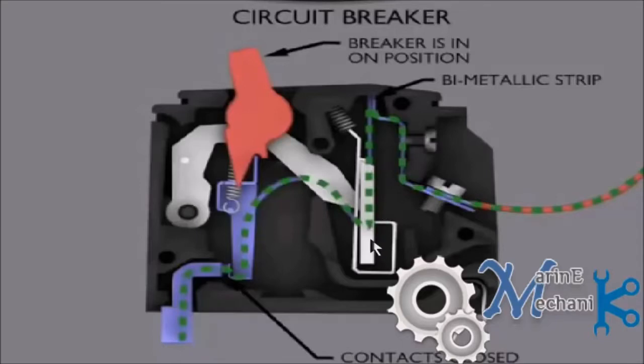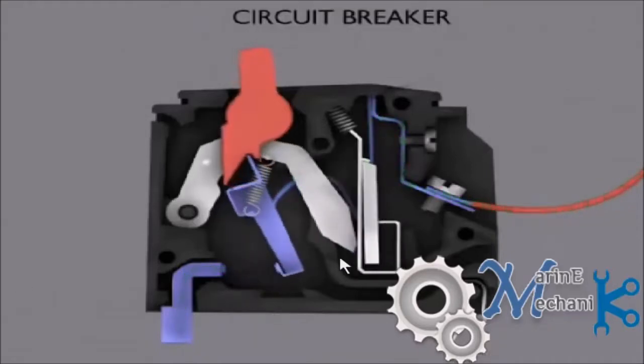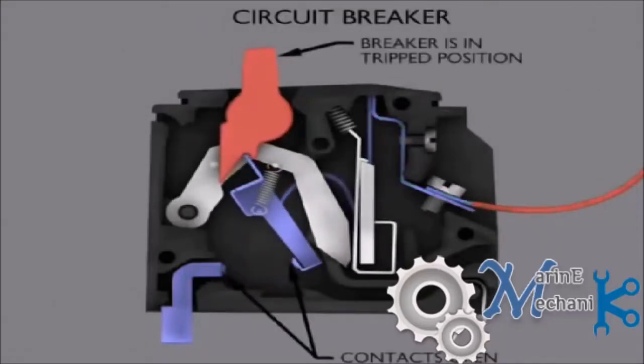let's say for example 40 amps, what happens is this expands and then the link is taken or pulled back so that the contact is open, and no more current supply passes through. So now the current flows through this link and through this wire, through this contact, and goes to the output terminal. Now let's see what happens when the overload gets. So this is how it works. I'll show it once again.